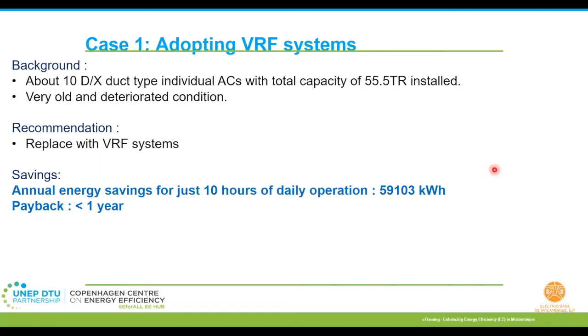Here, this was for an office building wherein they had about 10 direct exchange duct type individual air conditioning units, with a total capacity of 55.5 TR. They were very old, deteriorated, and not well maintained. So instead of replacing them with a similar type of air conditioning units, we recommended they go for a VRF system, to cater to all the 10 zones that they wanted to condition. Once after installation, they measured and saw that they were achieving about 59,000 units per year energy savings. And this is an office building, so this saving is only for about 10 hours of daily operation on weekdays.